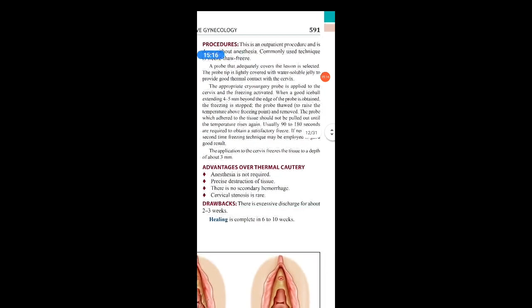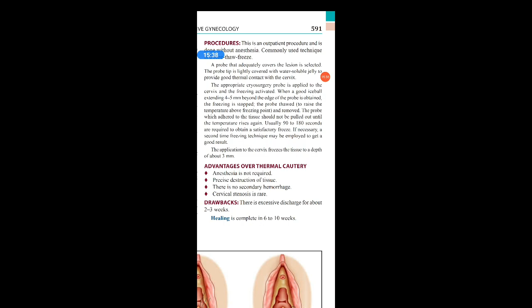The freezing is stopped, the probe thawed, that is to raise the temperature above the freezing point, and it is then removed. The probe which adheres to the tissue should not be pulled out until the temperature rises again. Usually 90 to 180 seconds are required to obtain a satisfactory freeze. So 90 to 180 seconds we can keep that probe, and it should not be pulled out until the temperature rises again. This is the method.